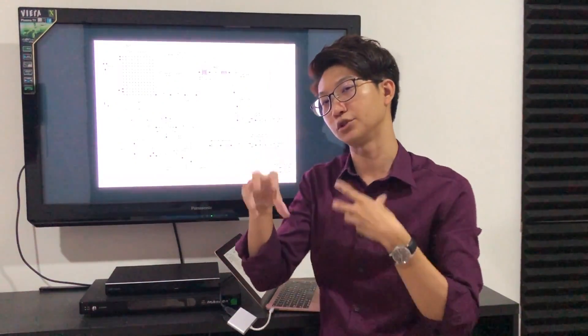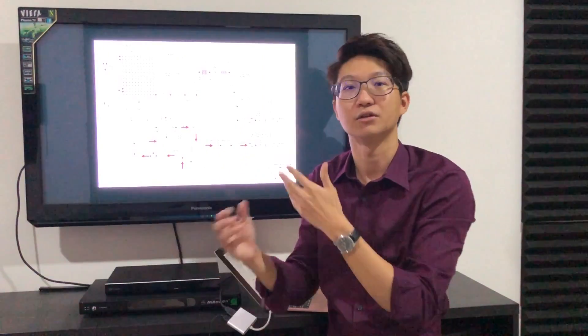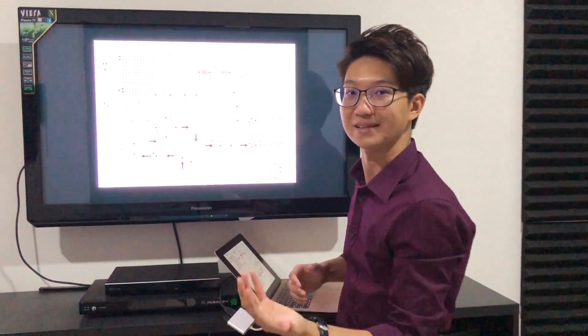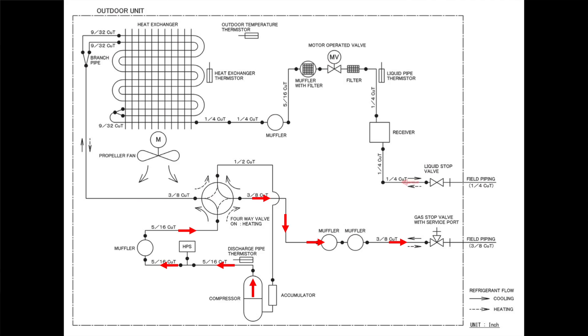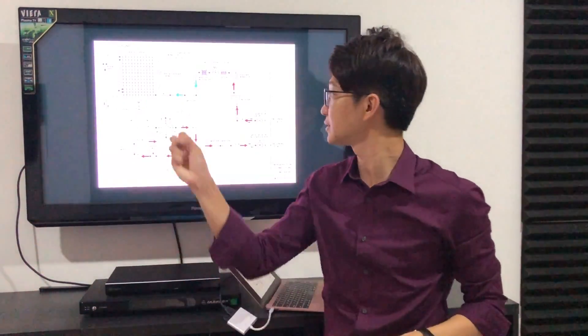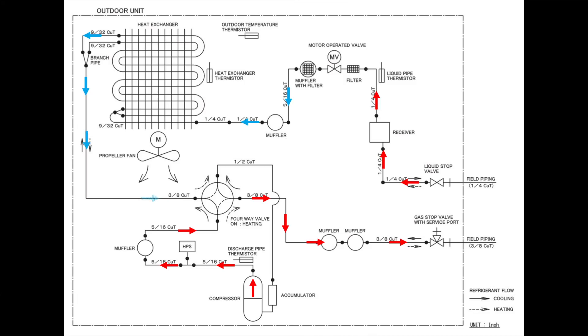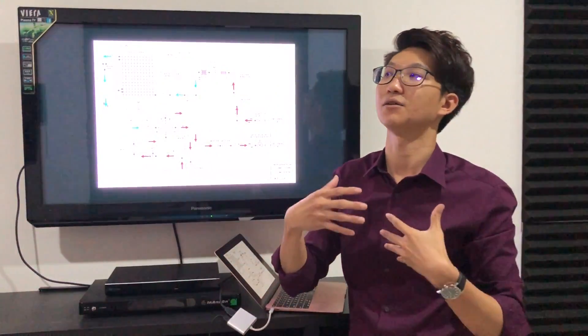When you press the remote controller and switch to heat mode, the same process begins with the compressor producing hot refrigerant gas, but this time the four-way valve turns so that the hot refrigerant gas goes straight to the indoor unit. The indoor unit now undergoes condensation — it becomes the condenser — releasing heat into the room. The refrigerant then comes back, goes through the expansion process, and flows through the outdoor heat exchanger, which now becomes the evaporator. This allows the heat pump to absorb heat from the outdoor ambient air, because the expanded refrigerant is very cold. That is how heating mode works.